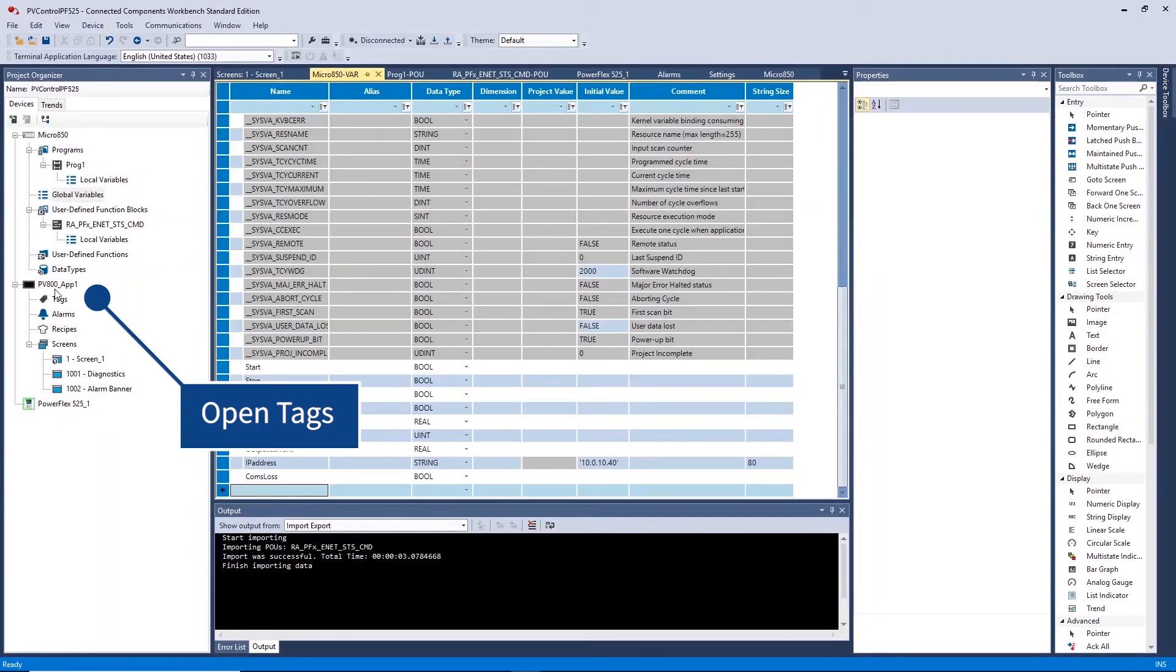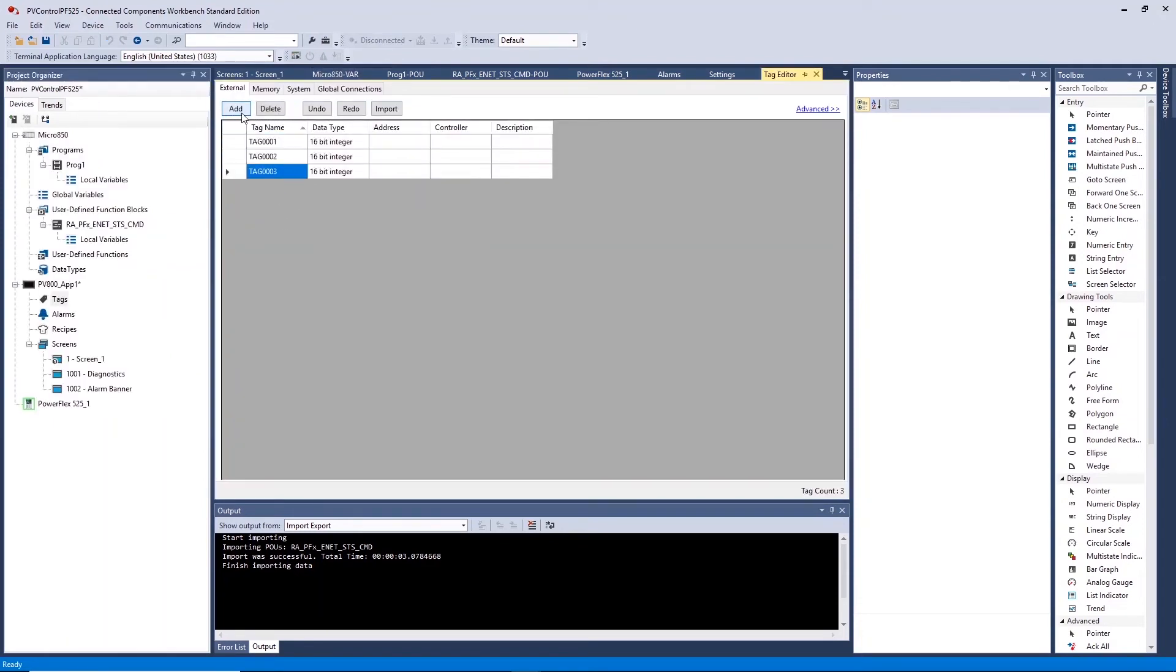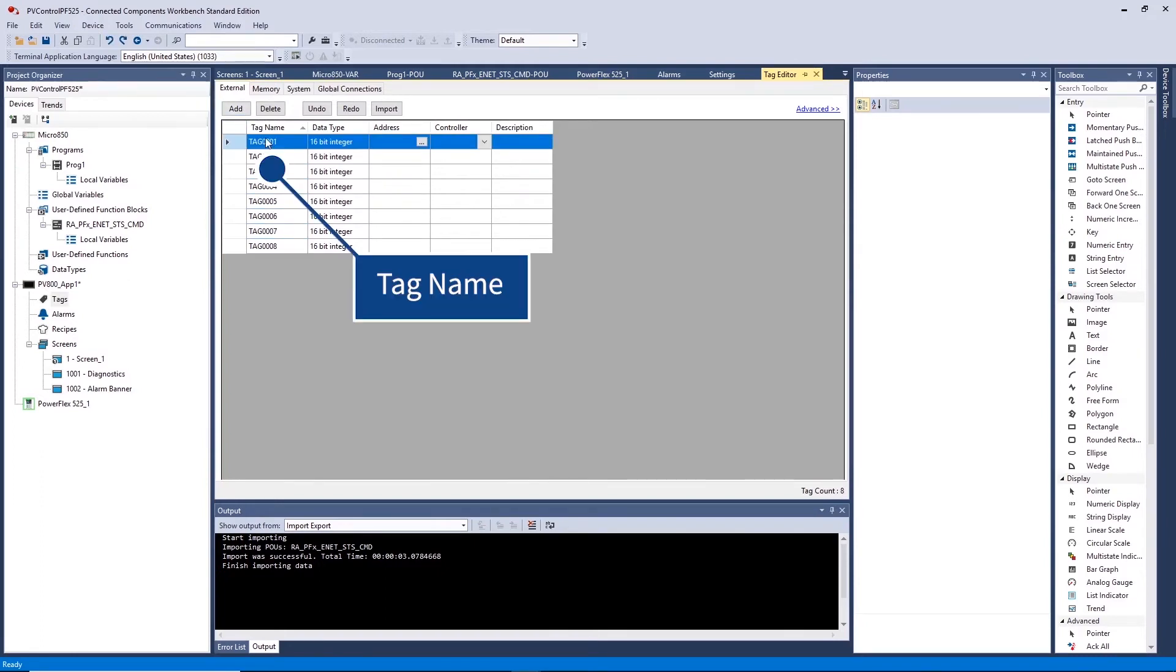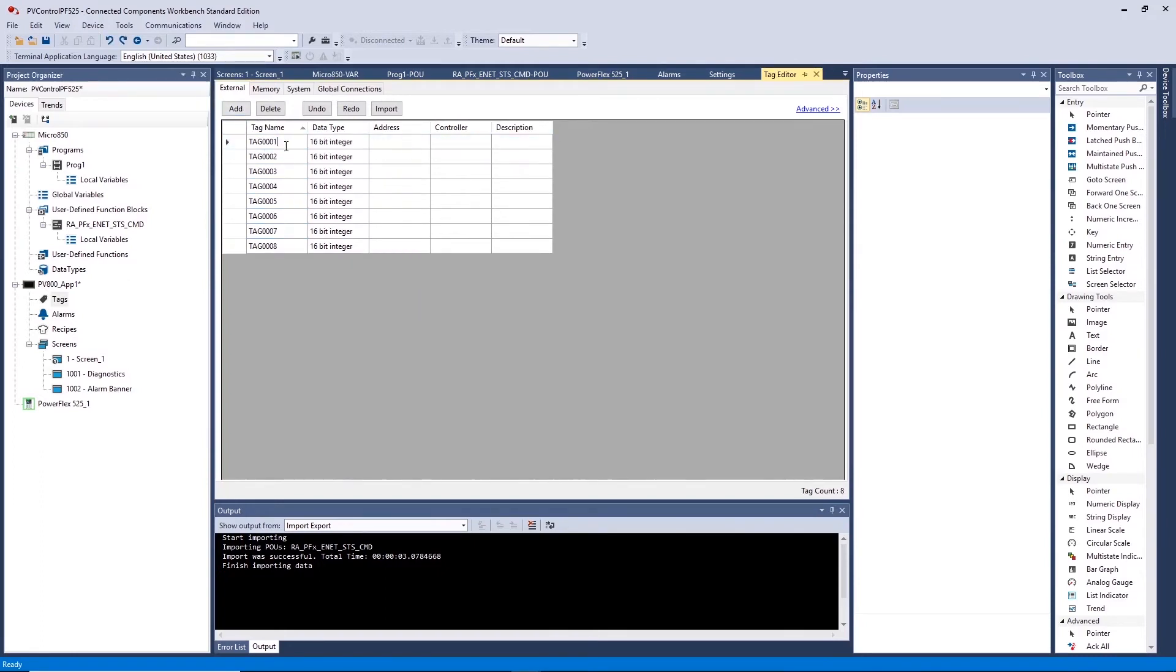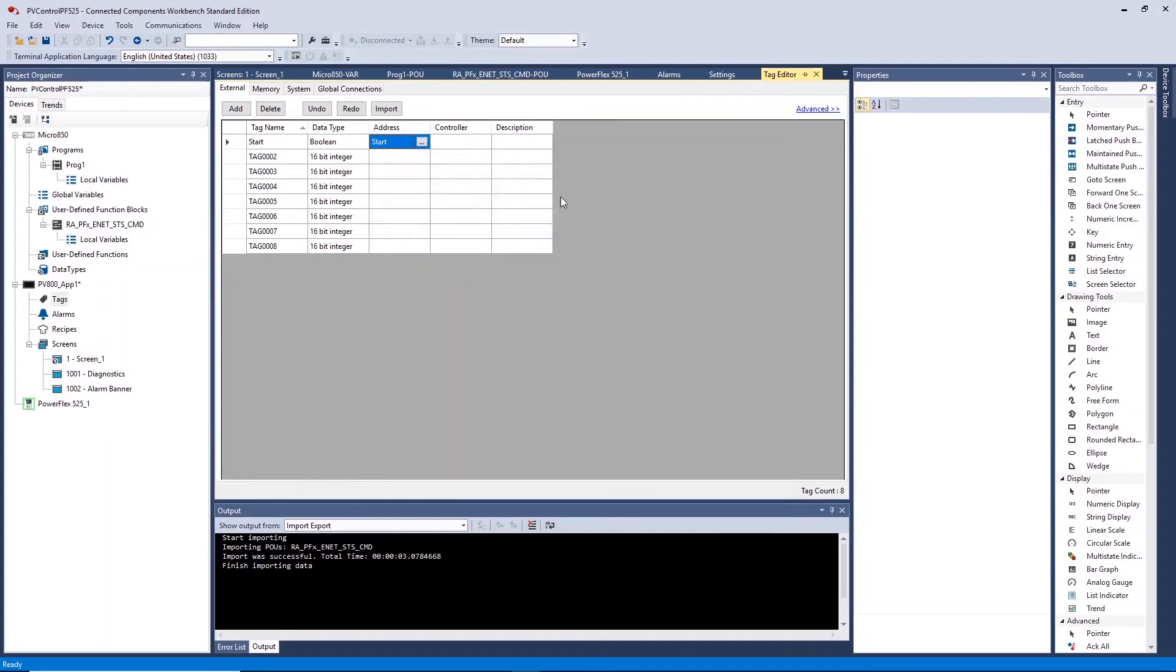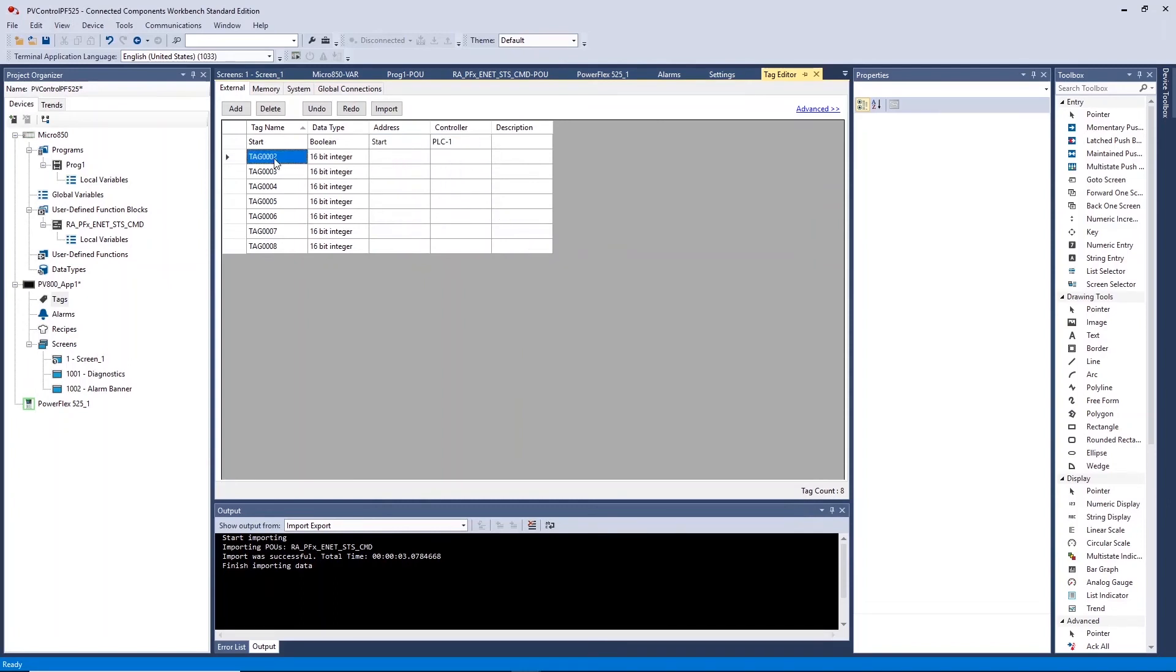The Tags tab allows you to create HMI tags and link these to controller tags. To create each tag we will need to fill in the following: Tag name allows for renaming of the tag referenced by the HMI, Address specifies which tag to reference to, and Controller specifies which PLC to reference.